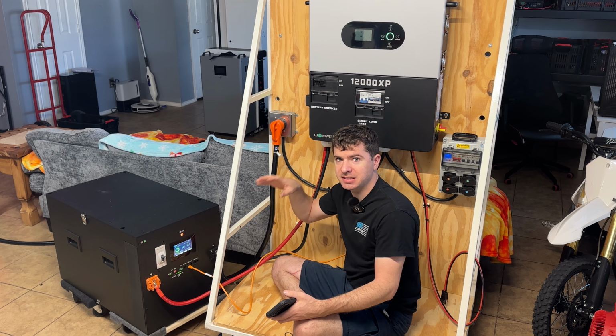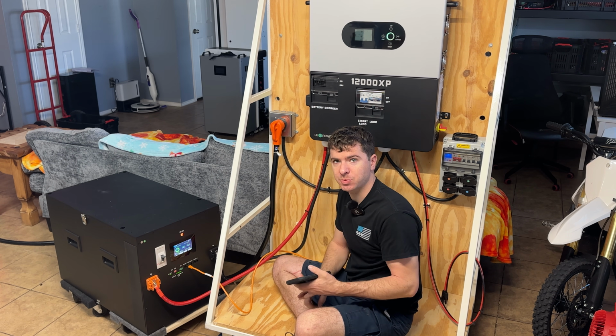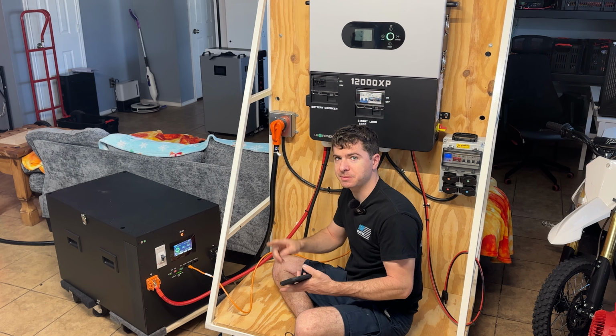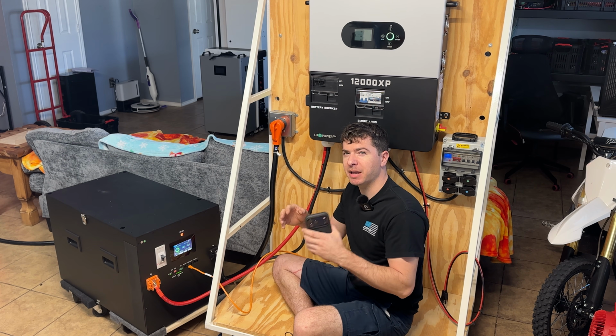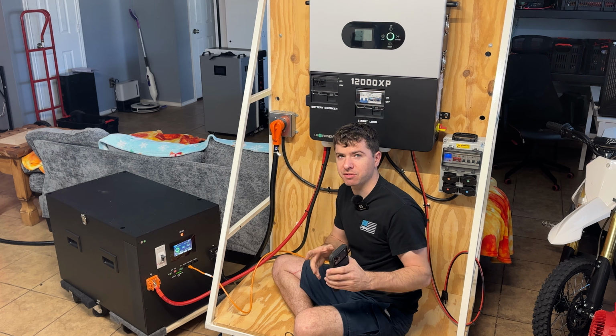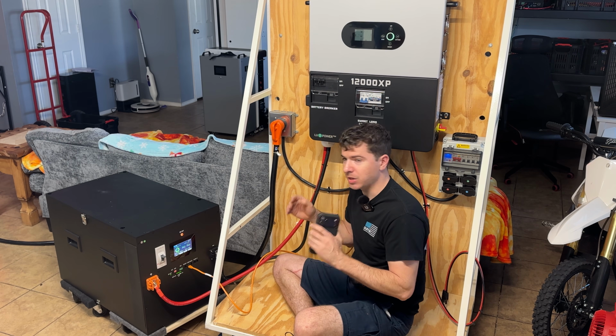From everything I've seen, this thing should be able to handle 300 amps. The BMS is rated for 300 amps, the breaker is rated for 300 amps, the fuse is rated for 300 amps. Personally, I probably wouldn't push it that hard, but I think 250 is still being very conservative. So I did go ahead and raise that limit.